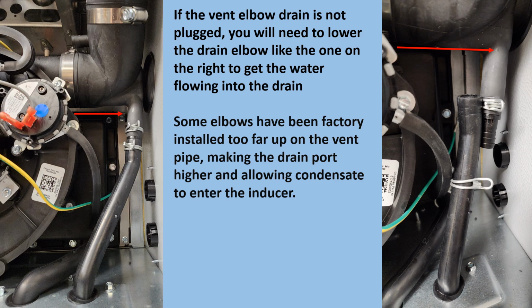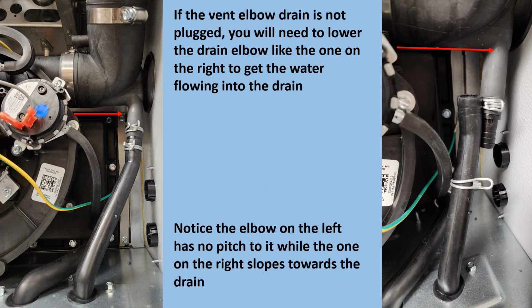Remember, that inducer, that water is not coming from the secondary heat exchanger, because the hole that the inducer goes over is halfway up the front cover. You'd be plugging every pressure switch and drain in the unit before you ever got up to that hole. Notice the elbow on the left has no pitch to it, while the one on the right slopes towards the drain.